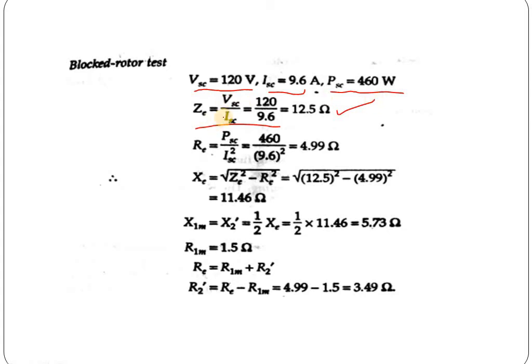Putting in the wattmeter reading of 460W and ammeter reading of 9.6A, we get the equivalent resistance value as 4.99 ohm. Now, we put this equivalent resistance value and equivalent impedance value to calculate the equivalent reactance XE. XE equals root over (ZE squared minus RE squared), which is root over (12.5 squared minus 4.99 squared), which equals 11.46 ohm.